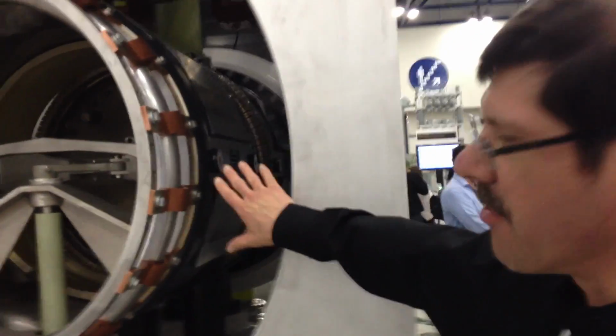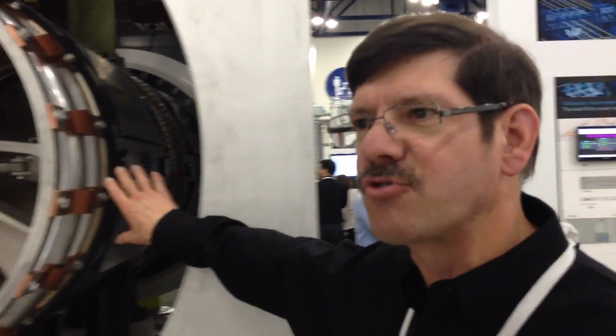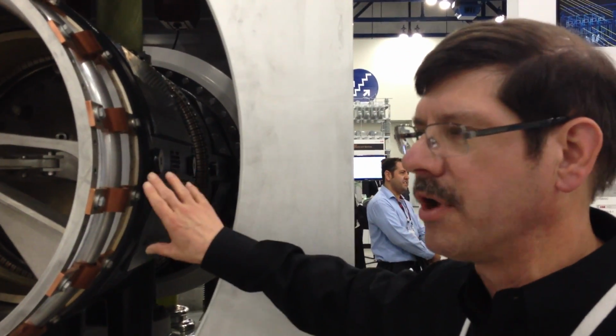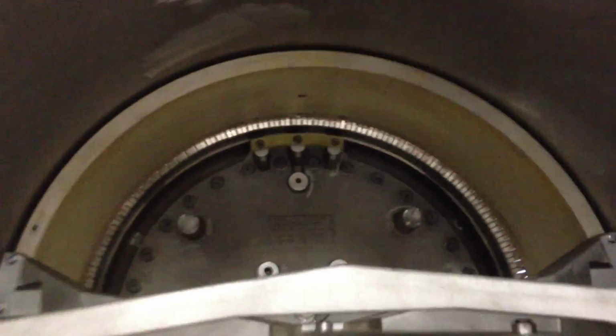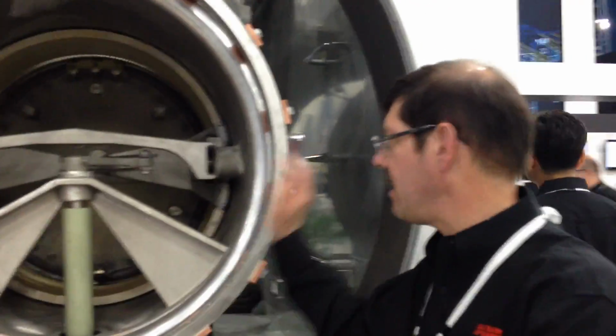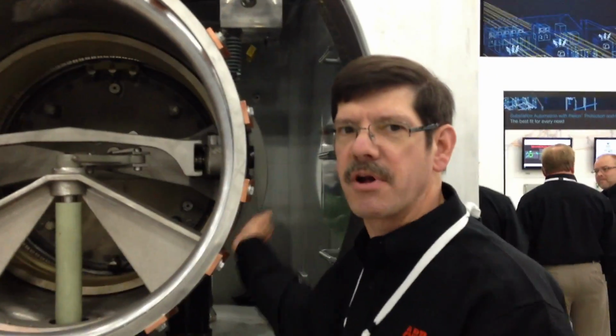This portion here is what's called the disconnect switch, the electrical isolation point - it's a no-load disconnect switch. Oh, and are these the contacts that I'm seeing in the round? Correct. It's in a cylindrical pattern where you would physically open it, allowing an isolated break point between your connecting isophase bus and the disconnect or generator circuit.